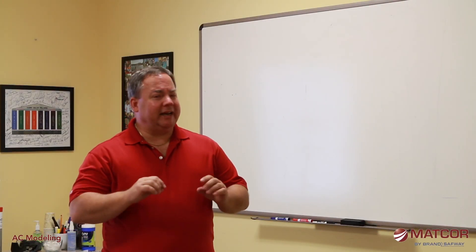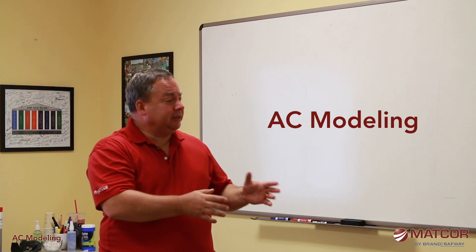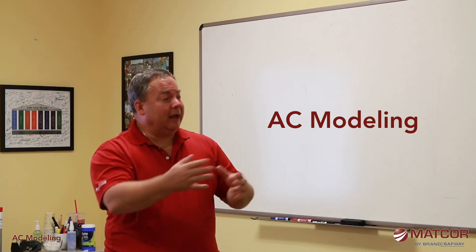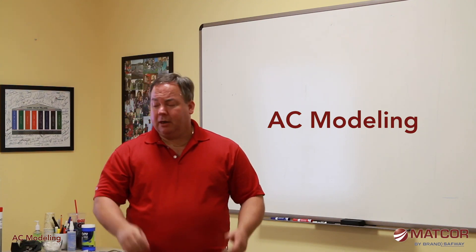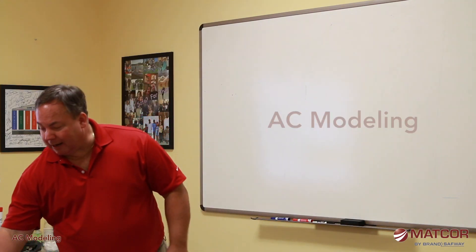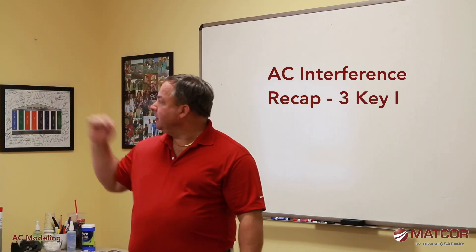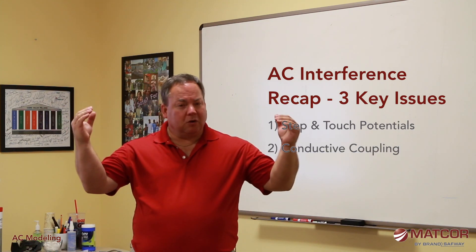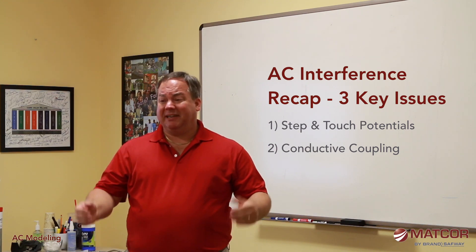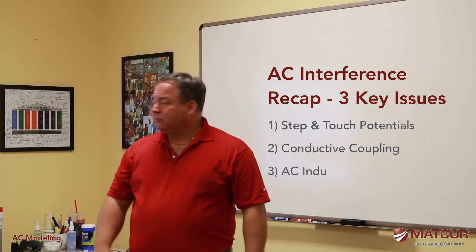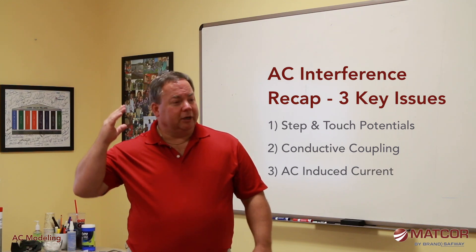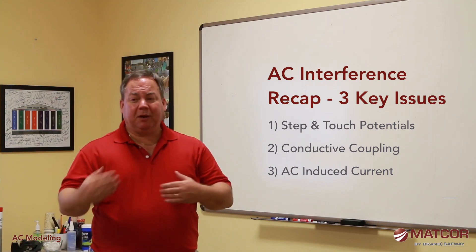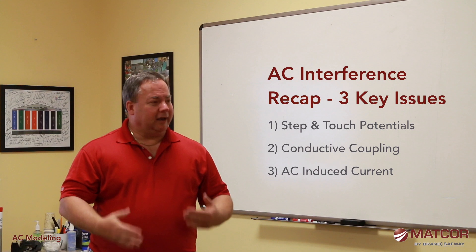In this segment we're going to talk about AC modeling. As a recap, there are three different issues: step and touch potentials, where we want to be below 15 volts AC; conductive couplings, where a fault condition dumps current into the earth and we want to make sure the pipeline is not damaged; and induced voltage, where the pipeline picks up voltage and current because it runs parallel to the transmission line.